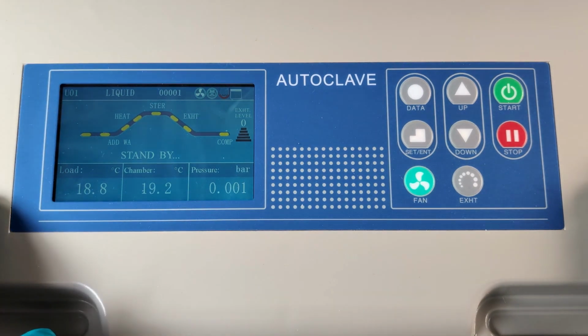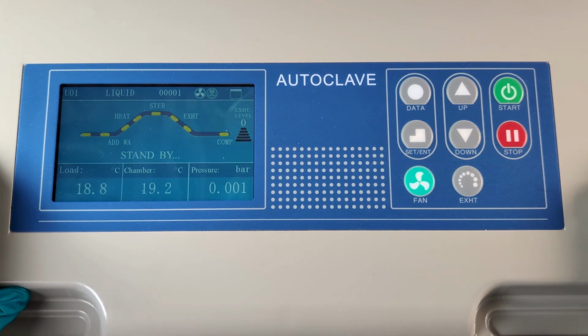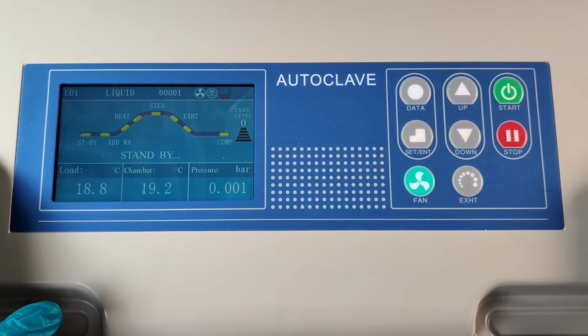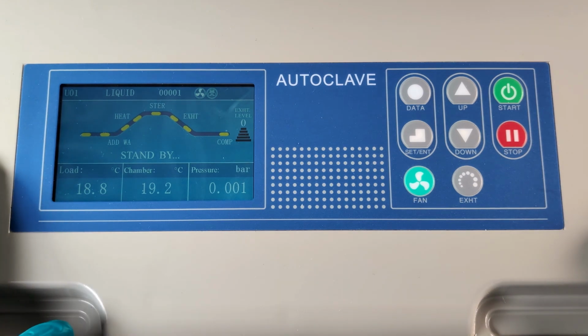Now, if program number 1 doesn't mean anything to you, it doesn't matter, because next it tells you in plain English what the program is. In this case, it's a liquid program for sterilizing various liquids in containers. To the right of that, you have the cycle counter. The cycle counter is a bit like an odometer and tells you how many cycles your autoclave has run. Also, this identifies each and every cycle that's been run in such a way that you can go back to it, recall it, look at the parameters, and either print them out or download them onto a USB stick, so that you have a continuous record of the cycles that you have run.